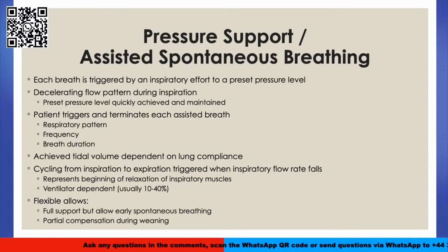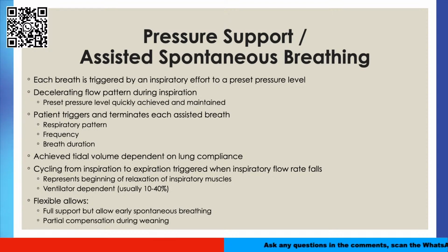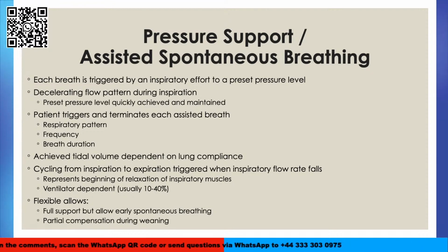I'm going to mention briefly pressure support or assisted spontaneous breathing. This is where each breath is triggered by an inspiratory effort to a preset pressure level. You get a decelerating flow pattern during inspiration, and that means that your preset pressure level is quickly achieved and maintained. The patient is triggering and terminating each assisted breath, and this will be dependent on their respiratory pattern, and they determine the respiratory pattern, the frequency and the duration of each breath. And the tidal volume you obtain will really depend on the patient's lung compliance.